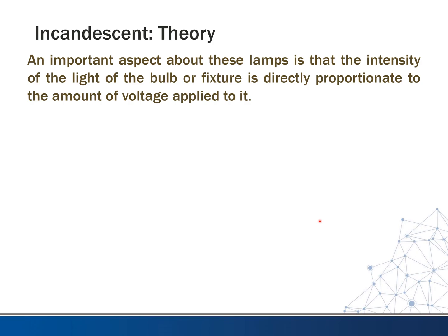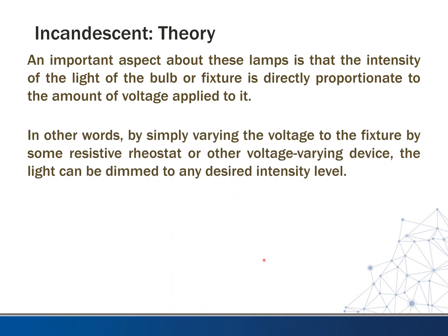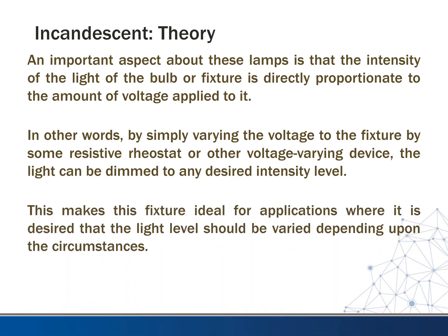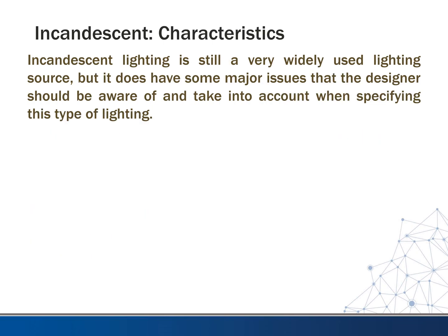An important aspect about these lamps is that the intensity of the light is directly proportionate to the amount of voltage applied to it. By simply varying the voltage to the fixture using a resistive rheostat or other voltage-varying device, the light can be dimmed to any desired intensity level. This makes this fixture ideal for applications where the light level should be varied depending on the circumstances. Incandescent lighting is still a very widely used source, but it has some major issues that the designer should be aware of.